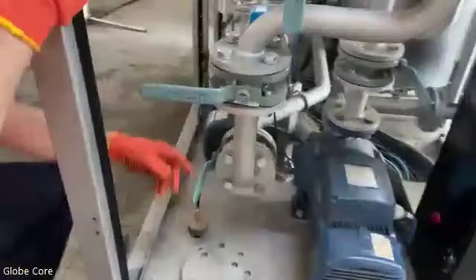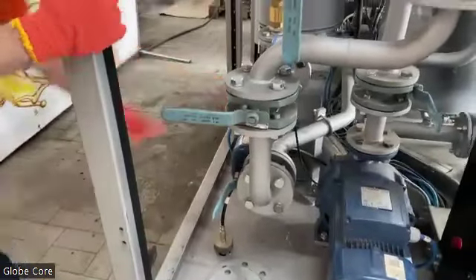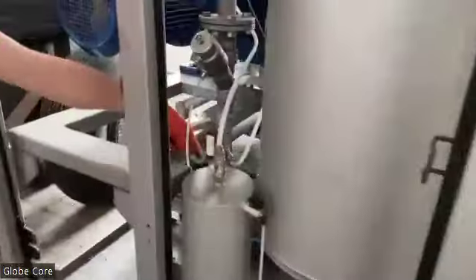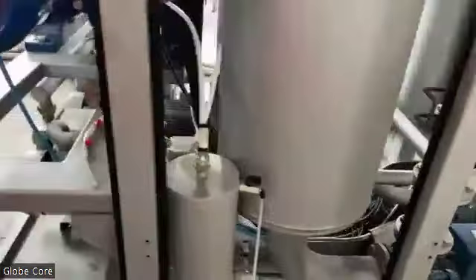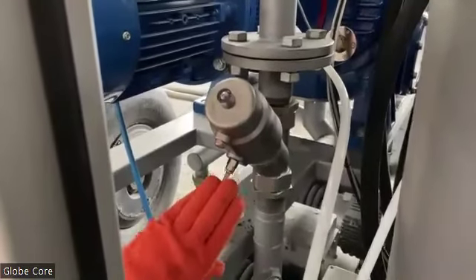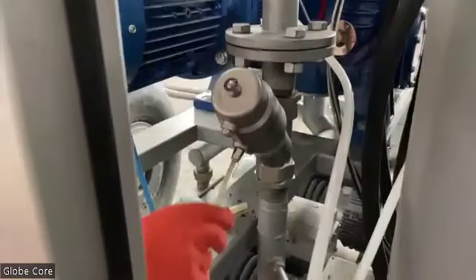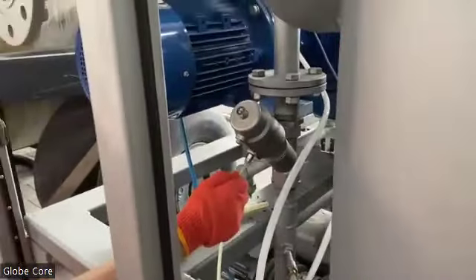Now, if we close this valve and open that one, oil will go to the vacuum chamber, through the cut-off valve. So normally it is closed and it opens when some pressure is provided to its inlet here. So if sufficient pressure is applied to this point, the valve opens and lets oil come into the vacuum chamber.